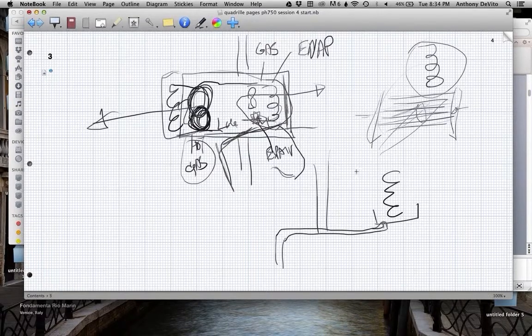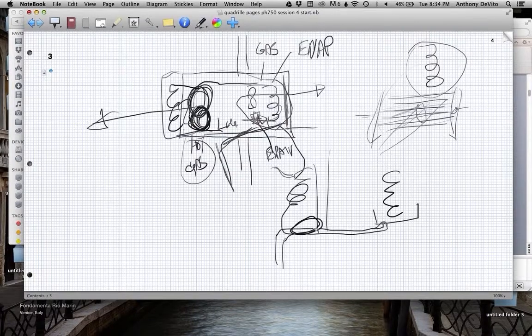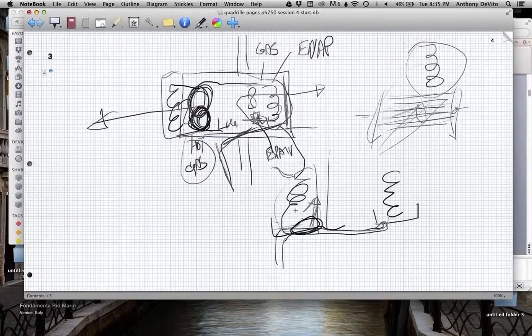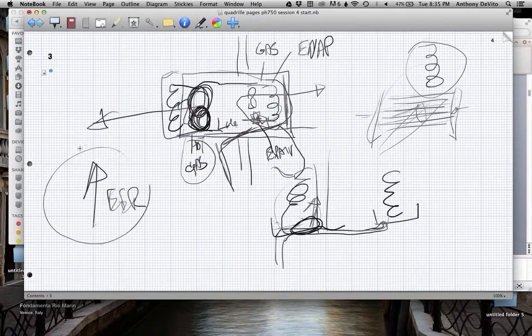The reason why you don't see the drip anymore is because now on the condensing coils, they drop one or two coils into the bottom of the pan, right? So what happens now is that the condensate, instead of building up, gets evaporated away by that coil in the back, so you don't get the drip. Not only that, but cooling with water makes it more efficient. So you raise the EER, energy efficiency rating, of the unit, plus you get rid of that pain in the butt drip, right?